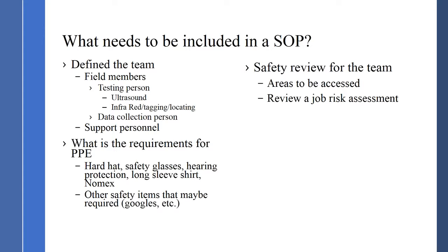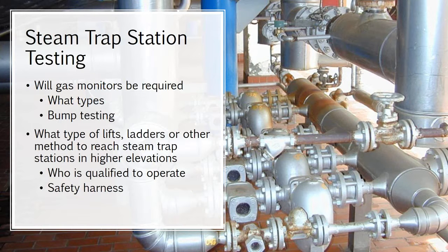Other devices that might be required: gas monitoring, such as H2S monitors. Bump testing the monitors — who's going to do that, and where will it be done? We also get into types of lift ladders and other methods to reach steam trap stations at higher elevations. The SOP will go through who's qualified to operate lift equipment and what type of safety harness they need, or whether the plant will provide the safety harness. All of that is part of the SOP for getting prepped for the steam trap assessment.